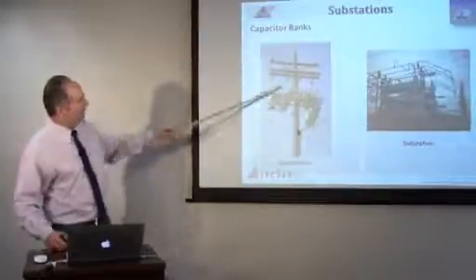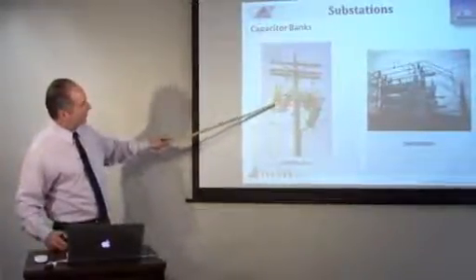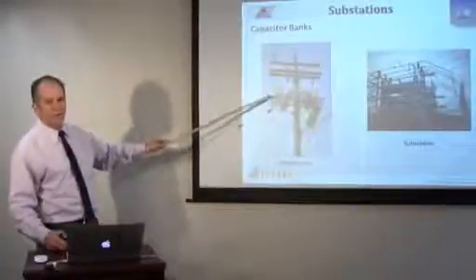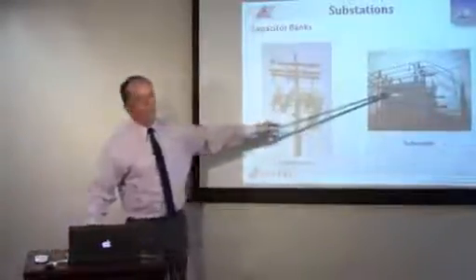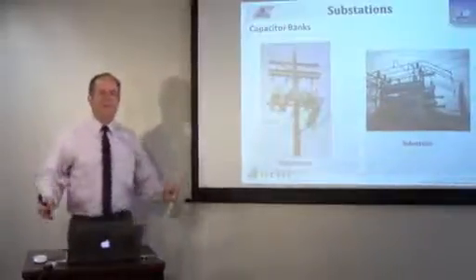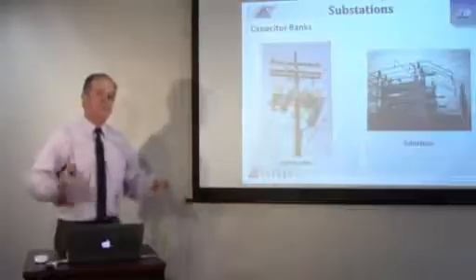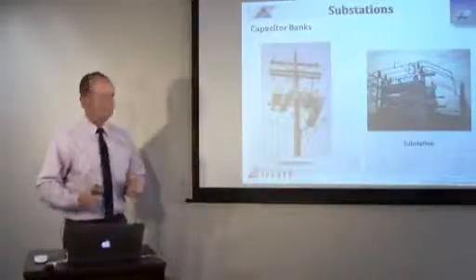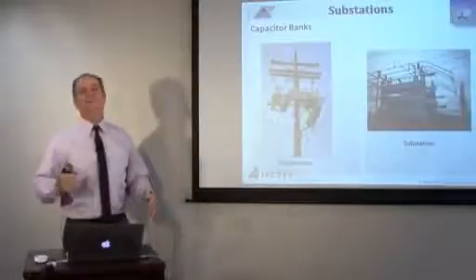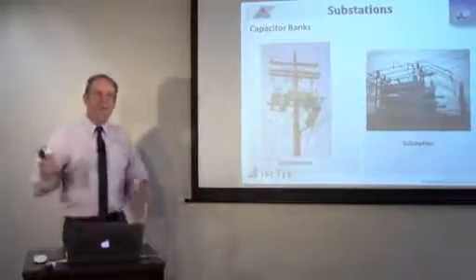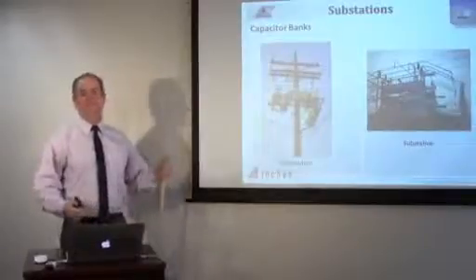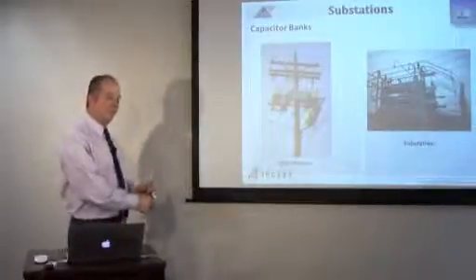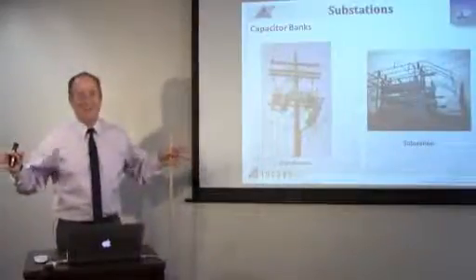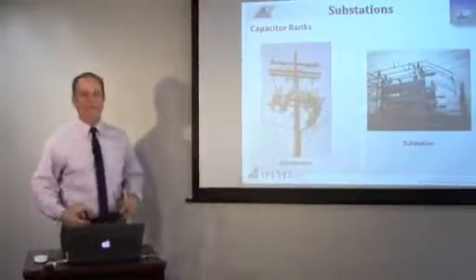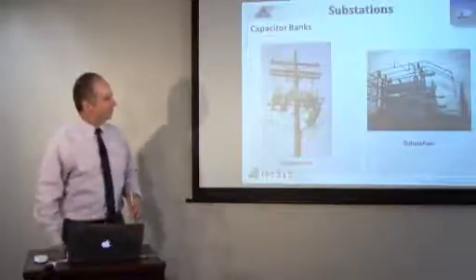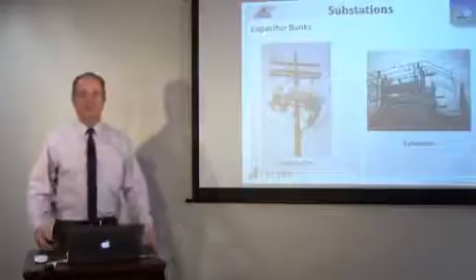So here's a capacitor bank on a distribution pole. You can see the capacitors here, one for each phase, and there are multiple units per phase. Here's a capacitor bank in a substation. There might be an industrial area where from 8 to 5 you need to turn on the capacitors, and just get that capacitor on there to compensate for all the motor loads, to reduce the current, improve the power factor, reduce the system losses, raise the voltage, all those reasons for capacitors. Okay? So that's substation and distribution capacitors.